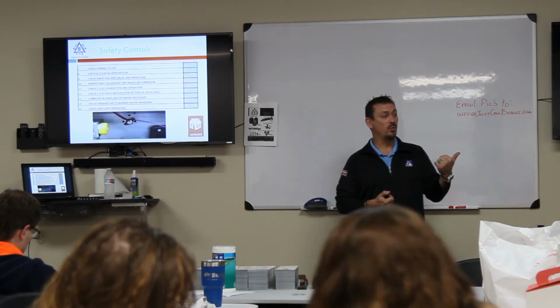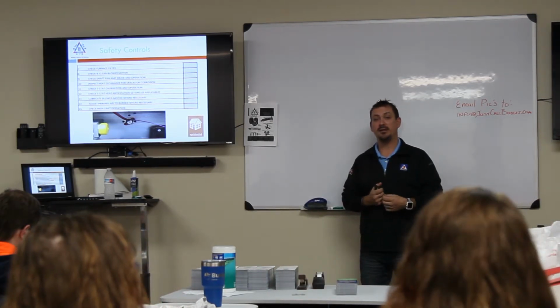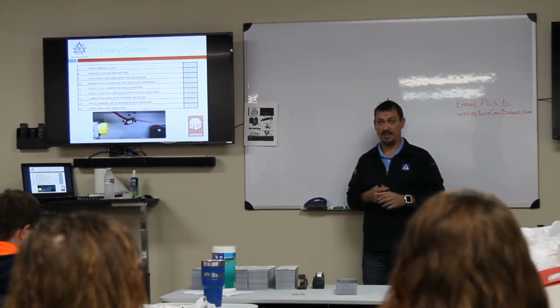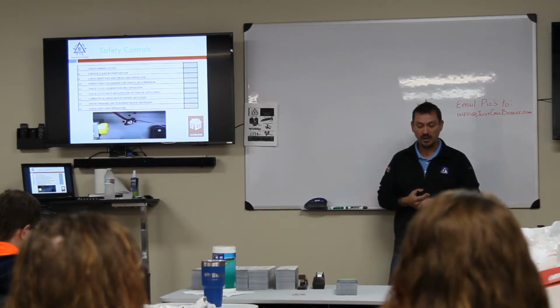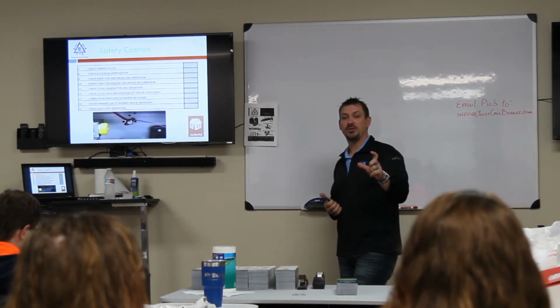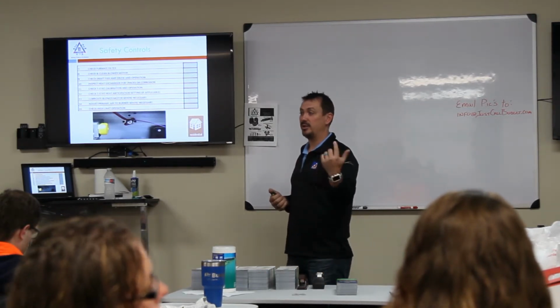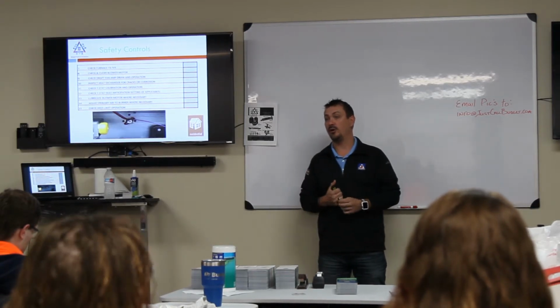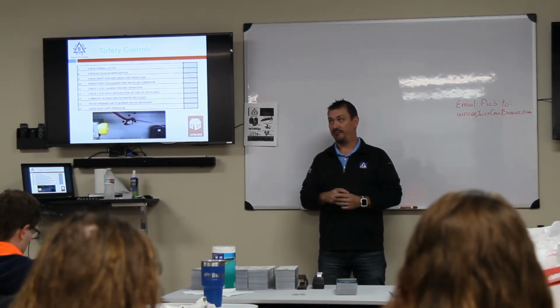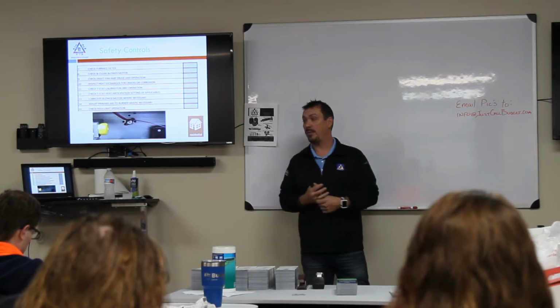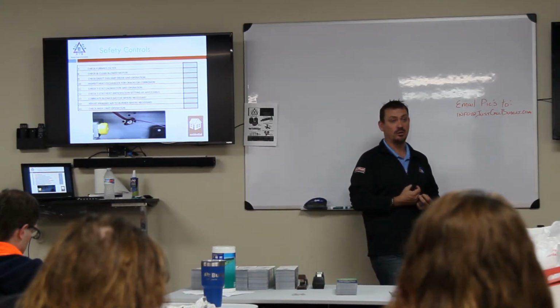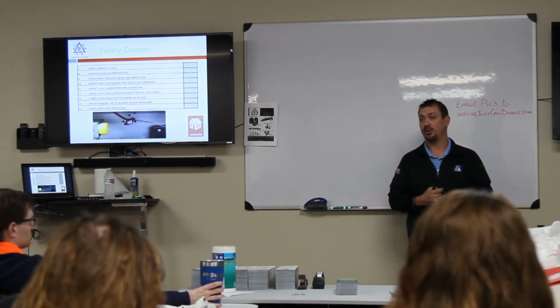And what happened, we did this one day, we had a pressure switch that came in out of the St. Peter's branch, it was on a Wednesday afternoon. And I took that pressure switch to show in my classes. I had a bunch of classes coming up where we were going to look at and talk about pressure switches. Friday morning, the pressure switch still showed bad. By Friday afternoon, I was doing another class, and all of a sudden the pressure switch showed good. Well, what happened? It dried out. Moisture got inside that pressure switch.